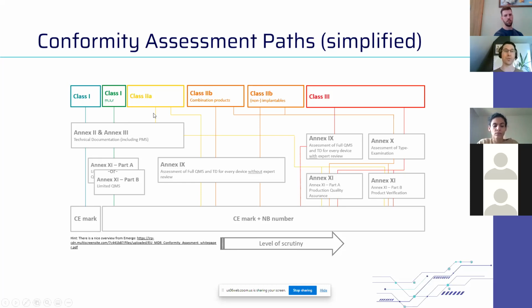Class 2A, of course, needs a notified body, and there are different ways to go about that, either with an assessment of the full quality management system and the technical documentation without expert review, or by just looking at the technical documentation. The more assessment you have beforehand, the more flexibility you will get in making independent decisions. Meaning if you go through Annex 2 and 3, your notified body will only look at this product. If you want to bring out the next version of a product, which is maybe significantly changed, you will need to do that again.